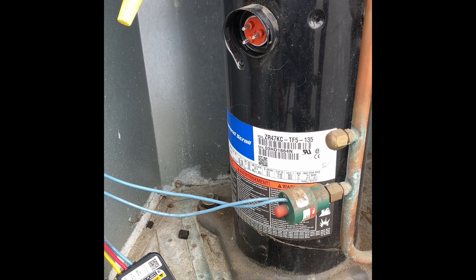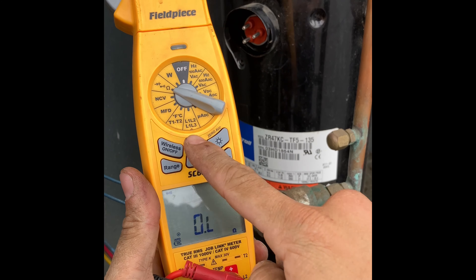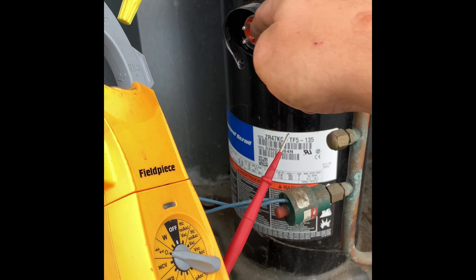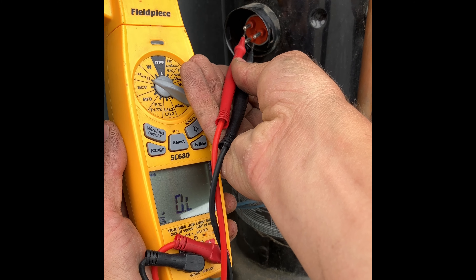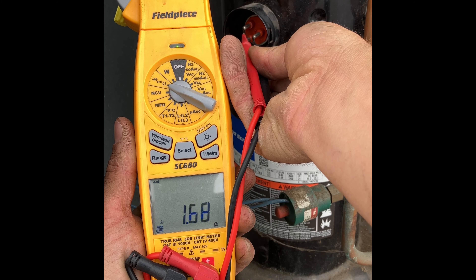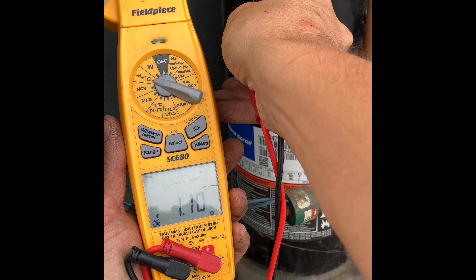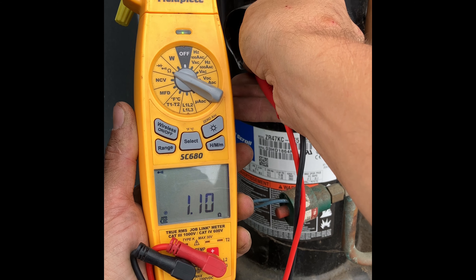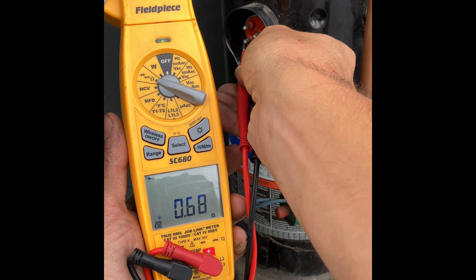Now another thing we can do to check for a failed compressor is take out our multimeter, set it to ohms, and check resistance between each winding — because this is a three-phase compressor. Going from one to three: 1.68. One to two: 1.09. And two to three: 0.68.